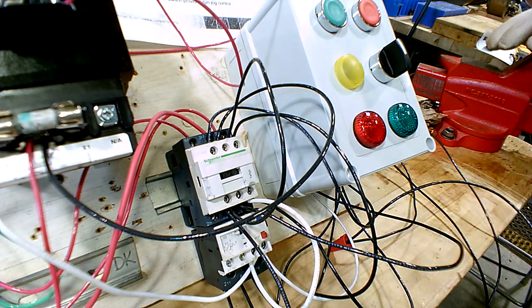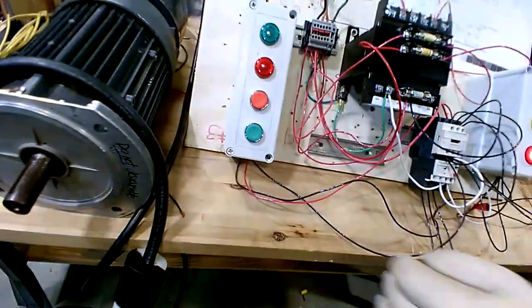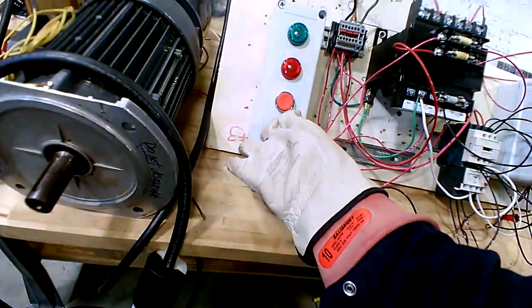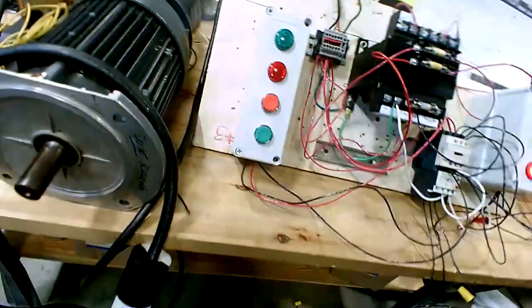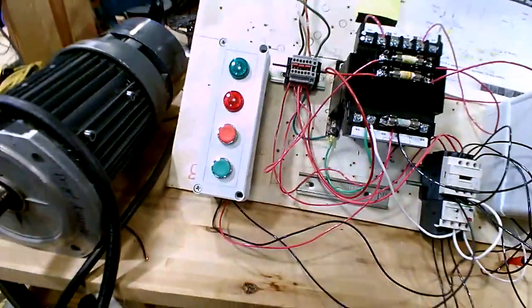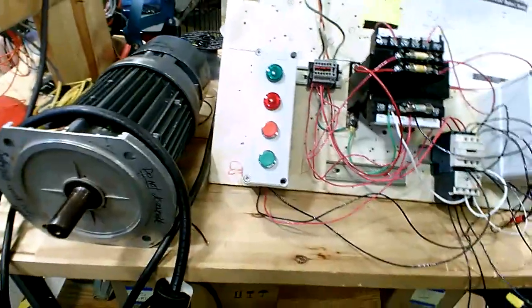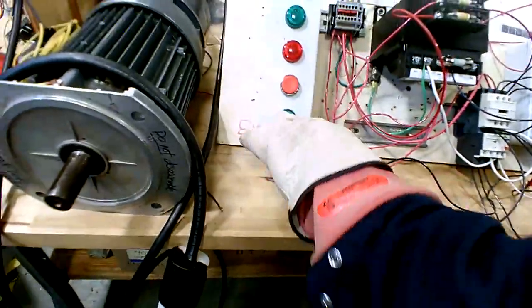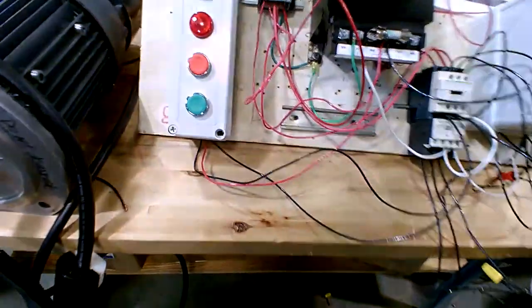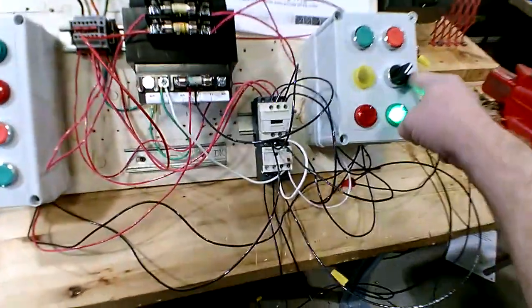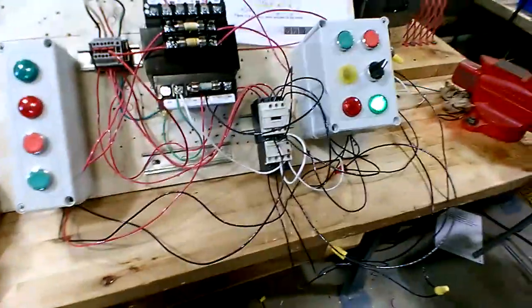So you should be able to hit it. You go to run now. Hit start over here. Let go. So you're actually in jog right now. Flip it over the other way, and I bet you switch it backwards. Now hit start again. Yeah, we've got the wires on the wrong contact in there. So your run is over here and your jog is to the left.